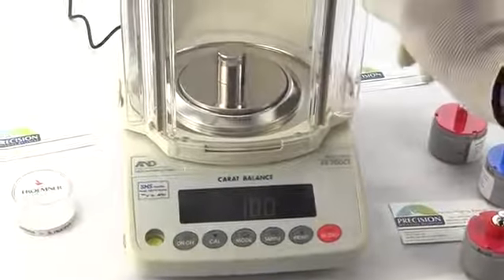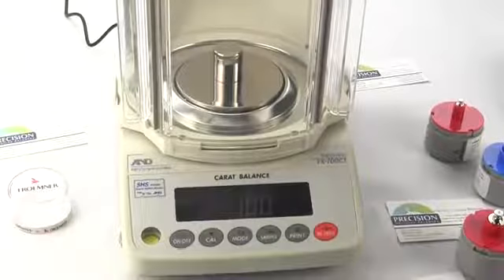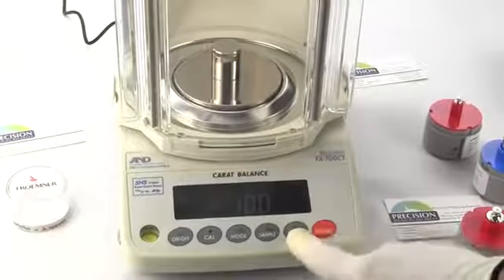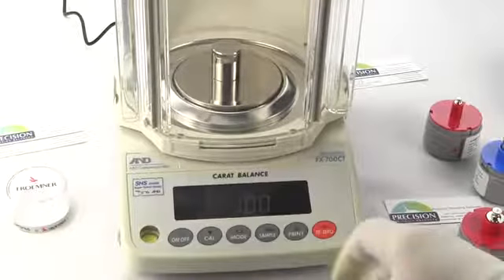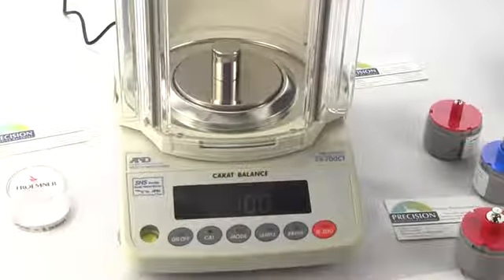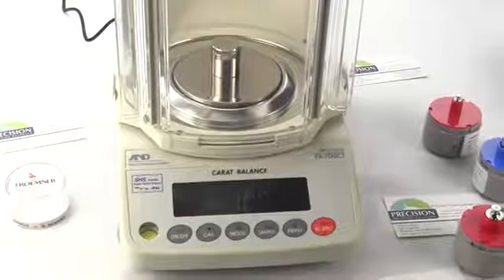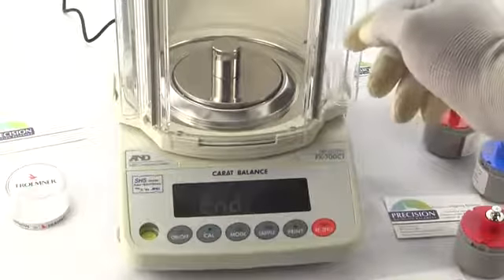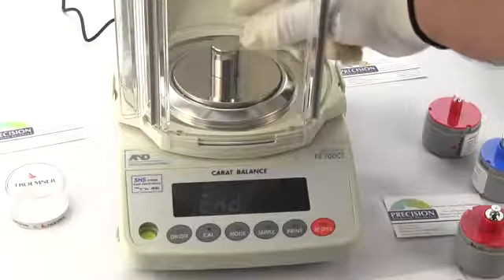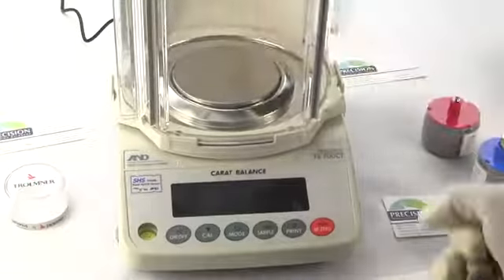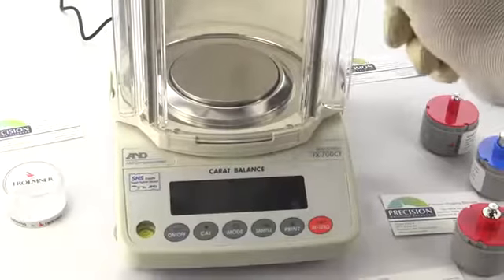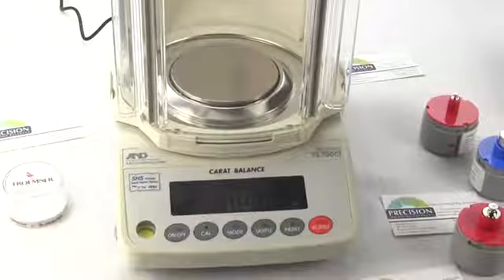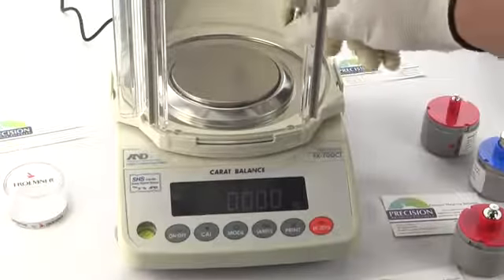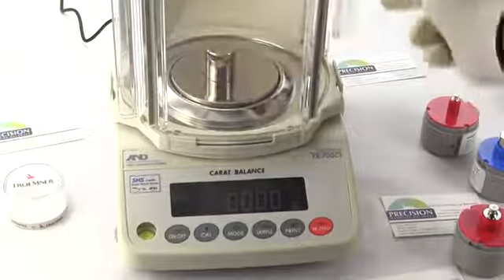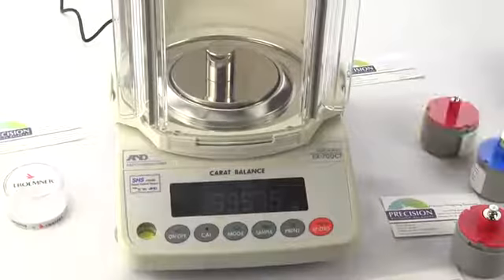And once the weight is there, we want to press the PRINT key. And again, in the upper left hand corner, you'll see that arrow, meaning that it's storing the value for the 100 grams. Now it says END. We remove the calibration weight. The balance returns automatically to the weigh mode, and then we can put our weight on the balance, and the balance is now calibrated.